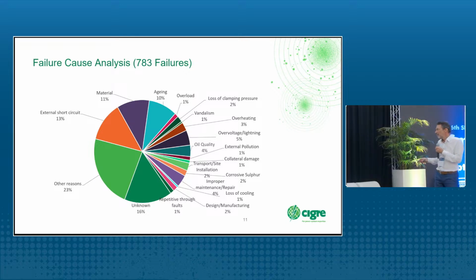Nevertheless, 23% of the failures are due to other reasons. Unfortunately, I do not know any other reason which could be possible, but 23% is other reasons, and 16% is unknown. So we guess that the people didn't want to say unknown, so they cross-checked here other reasons. So this shows that failure investigation is not properly done. And of course, this is quite important, because if you want to improve a product, you have to know why it fails. So that is one of our suggestions to the operators, that they do a proper failure investigation.